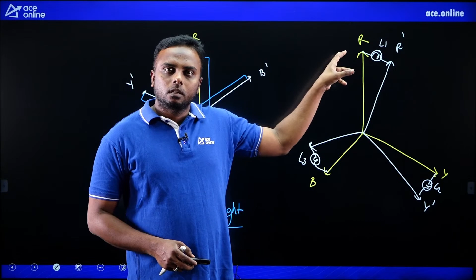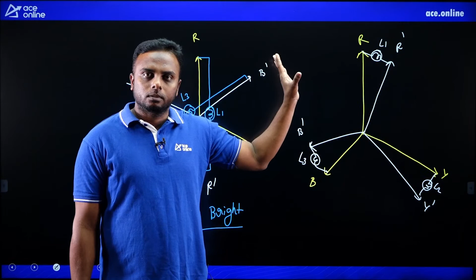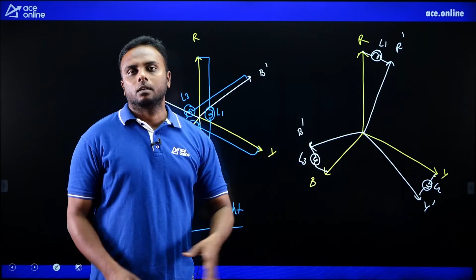The switch, connecting the alternator to the bus bar, should be closed only when these lamps are dark, because only in the exact dark position can we say the two systems are exactly in phase. Otherwise circulating current will occur. So we close the switch in this position. But here also the lamps are dark, and in this other position too the lamps appear completely dark. So how can you identify which position is the exact in-phase position? That is the drawback of this method — we cannot identify the exact dark or in-phase position of the alternator and bus bar phases using this first method.